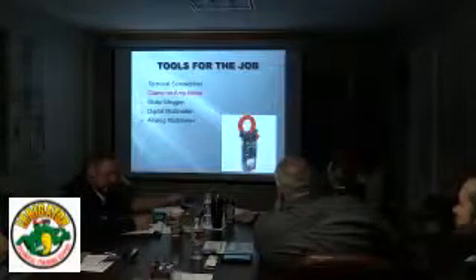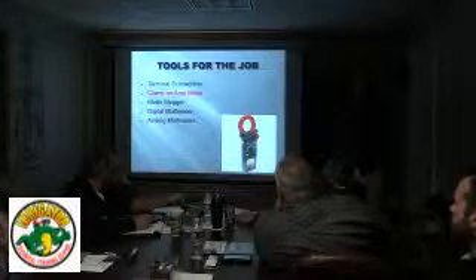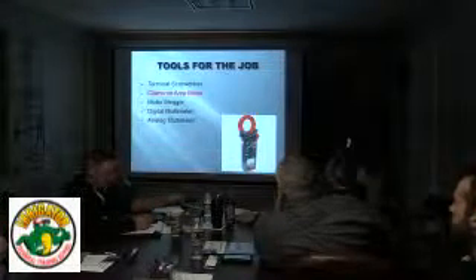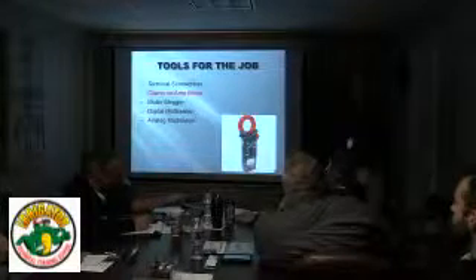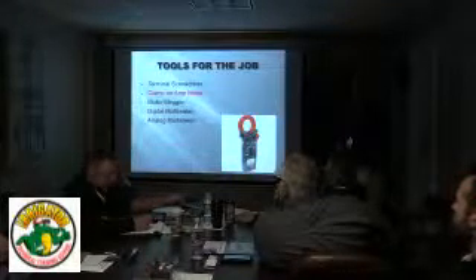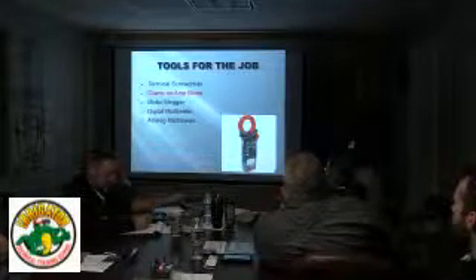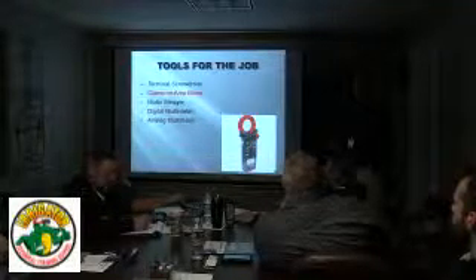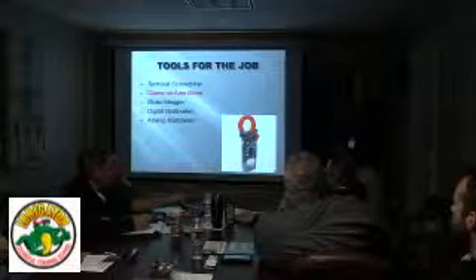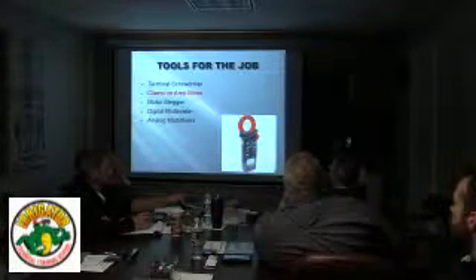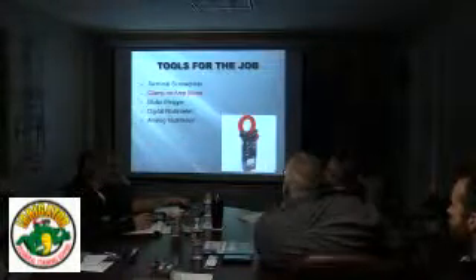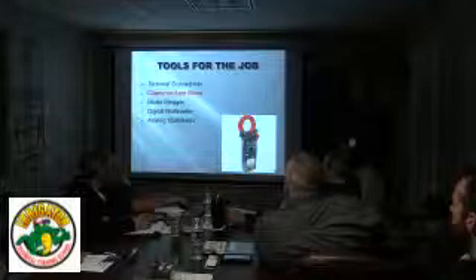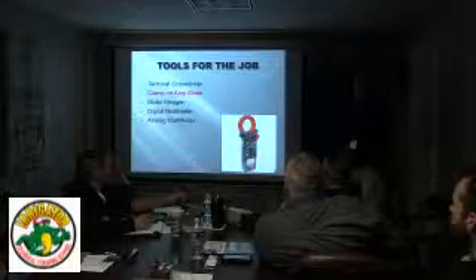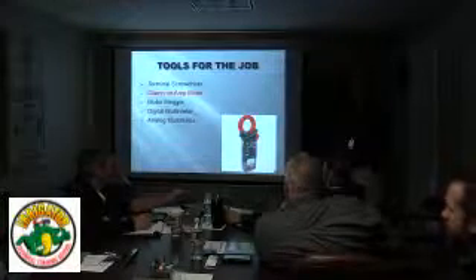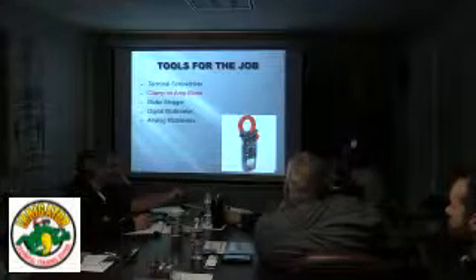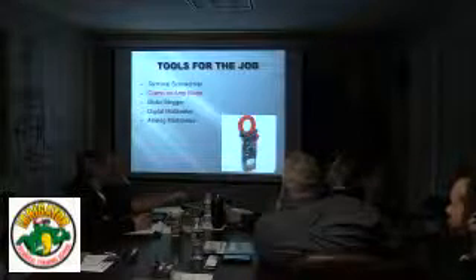Clamp on amp meter, those are pretty handy, not absolutely necessary, but a lot of times when you're troubleshooting a drive or a motor or something, a clamp on amp meter can be handy. Sometimes if a drive won't run full speed, we might check the incoming current on all 3 legs, and if one of them's gone or half of what it should be, that would indicate some bad input diodes on a drive. Same thing on output of a drive. If it's faulting on overcurrent or motor problems, you might put a clamp on amp meter on all 3 motor leads just to see if they're all within tolerance. So occasionally you would need a clamp on amp meter.